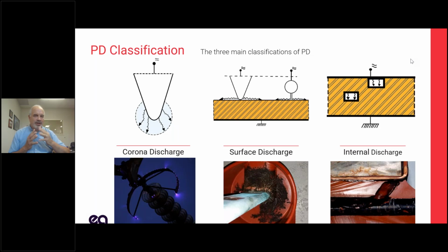This is characterized by a buzzing, humming noise you can hear, a lot of radio noise that's generated. In the right light, you can actually see blue sparks coming off the conductors, and it's a result of geometry, construction, humidity. It's not necessarily going to lead to catastrophic failure right away, but its big problem is that it tends to hide more destructive forms of partial discharge.